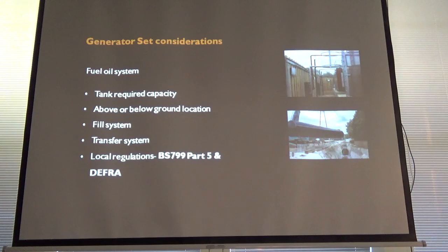twice working, and if you've got additional units on there that you're going to add for a tenant, in addition to say a life safety unit, again you can size that delivery system initially for day one or day final, whatever. Again, it's all these considerations that then come into play. But this is a positively pressurised line, therefore double skin through the building. That may be a single skin tank in a bunded plant room, or it could be a bunded tank itself, come as a pre-built bunded tank unit. But either way, secondary containment and leak detection, always important and key.